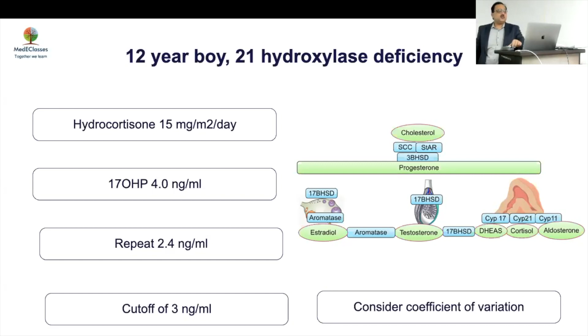So now, how do you use the CV? Which amount is acceptable and which is not acceptable to you? So as a rule, as I said, 10 and 15 is the target. But if your CV is more than 20%, you don't accept the result. This is a general rule.